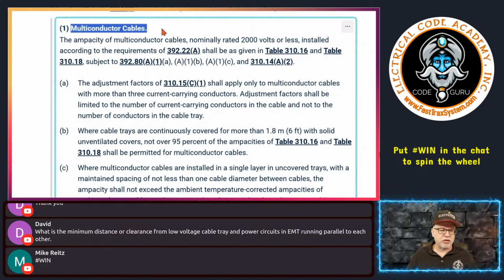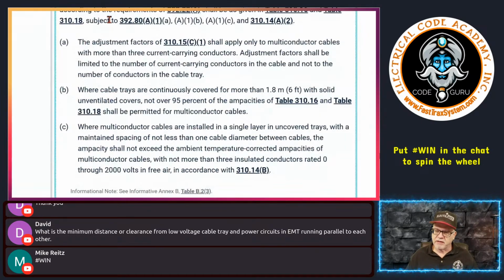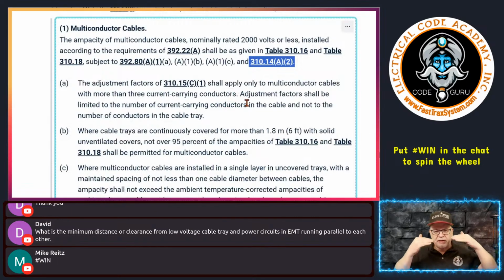Again, we're talking multi-conductor cable, A. Now here's where it tells you subject to all these right here, which are these down here. And of course this little reference right here is that nifty one that says if you have two different ampacities based on the condition of use, then you have to go with the lesser one. But we do have an exception: if the one with the lower ampacity is due to, say, a higher ambient temperature, and it doesn't exceed that 10% of the lesser of the two, then you can ignore the one that impacts the conductor and makes it less current carrying, okay? That's what it's saying. So that allowance is in play. If that confuses you, you need to go back and watch that episode on that.